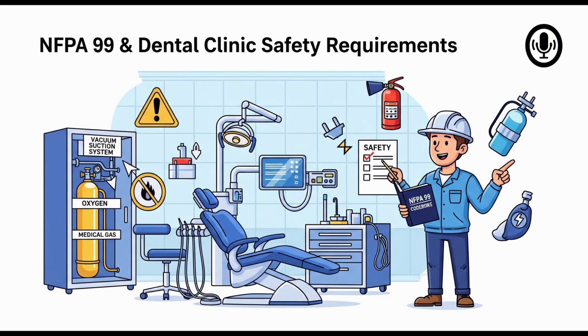That's right. In higher risk categories, like Category 1 or 2, you'd almost always need duplex systems, 2 compressors, 2 dryers, etc., configured so if one fails, the other takes over instantly. Right, for critical care. But for Category 3, like in many dental applications, the code says a single unit for the air system components is acceptable. This is a major cost and space difference, reflecting that lower risk assessment, a temporary loss of dental air isn't likely to cause immediate serious harm, unlike, say, loss of oxygen in surgery.